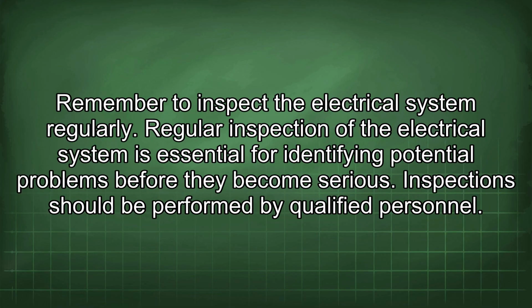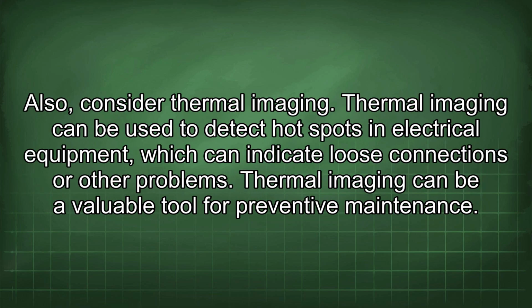Remember to inspect the electrical system regularly. Regular inspection of the electrical system is essential for identifying potential problems before they become serious. Inspection should be performed by qualified personnel. Also, consider thermal imaging. Thermal imaging can be used to detect hot spots in electrical equipment, which can indicate loose connections or other problems. Thermal imaging can be a valuable tool for preventive maintenance.